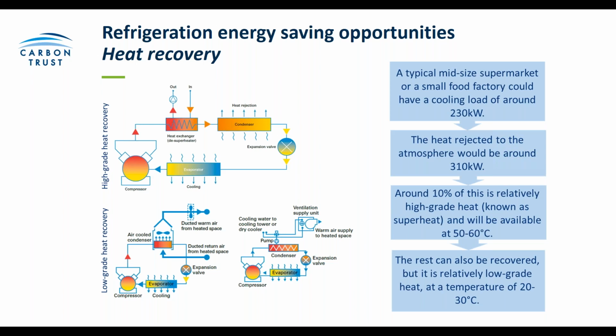Low grade heat can also be used in underfloor heating in cold stores and dry goods stores, and some systems can use a heat pump to raise the temperature of recovered low grade heat to exactly what's required by a factory. So there's lots of uses of heat that can be recovered, especially from a refrigeration system. But do bear in mind that when implementing a system like this, it's recommended that you do use an experienced contractor who is familiar with specifically heat recovery. It may be something that the Green Business Fund can support you in with our free audits and advice, but we'll get onto that a little bit later.